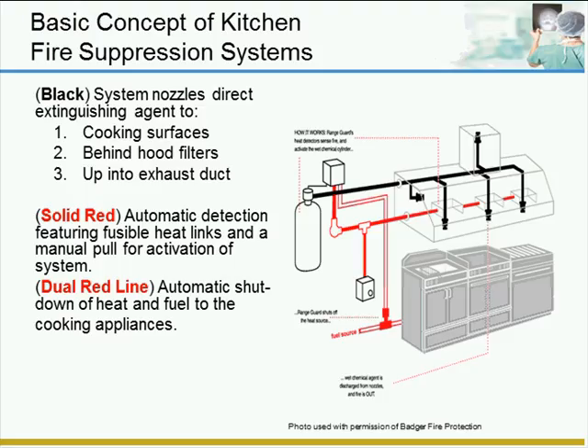These systems also have a solenoid. If you see the solid red on the bottom left next to the cooking equipment on the fuel source, that is the solenoid which will shut down the fuel source when the system is activated. These systems should be inspected, tested, and maintained by a qualified contractor every 6 months. And they will typically hang a tag on the manual activation switch indicating those dates, so check those.